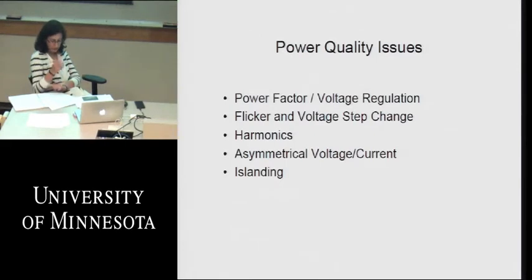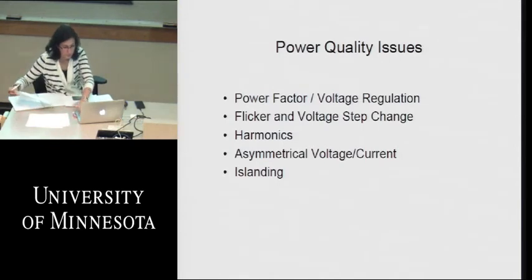Islanding is a condition when there's a fault on the system and your plant is on a line without any other generation on the line, but you still have load. You still have customers or cities on that line that you're feeding into. It's a very complicated issue in and of itself, and usually what we'd like to do is just get offline at that point, let the system restore itself, and then we put the wind power back onto the line after the system comes back up to its normal operations, when voltage and frequency are stabilized. Okay, next slide.